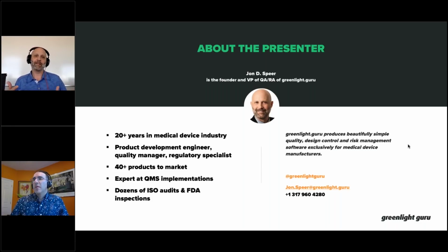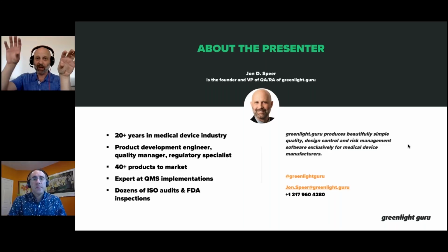The tricky part is that software developers speak a different language from FDA, ISO, regulatory speak. And so there's a relationship there. This is where it gets a little bit confusing, because in software speak, a common term that's used is a URS, user requirements specification. You probably remember earlier today in the presentation where I said requirements were like inputs and specifications were like outputs. Well, I told you the words get in the way, and it was a matter of semantics. This is one of those cases where we're certainly going to confuse matters a bit, so bear with me.